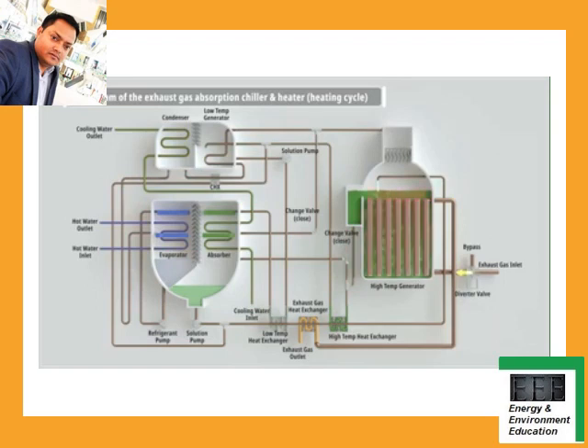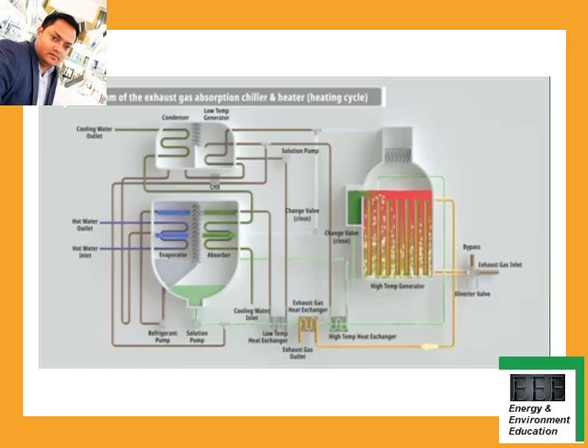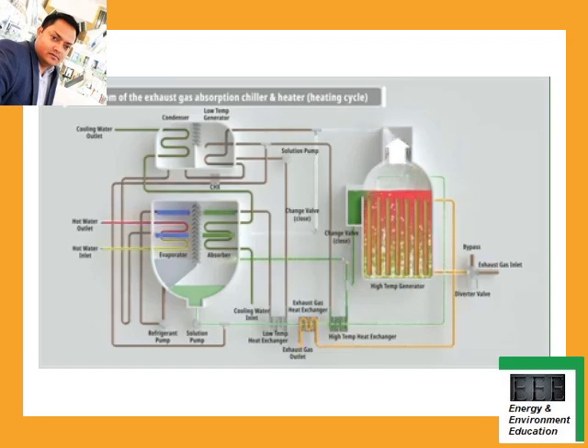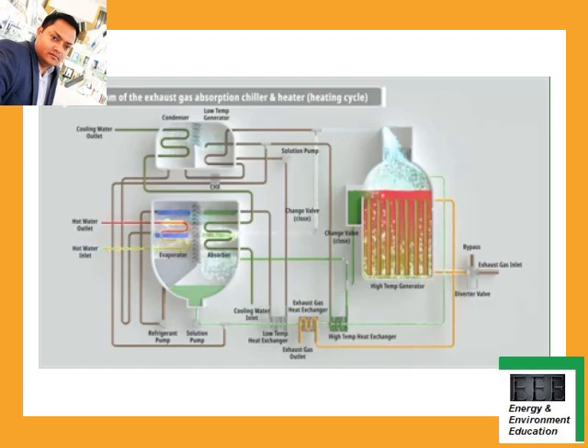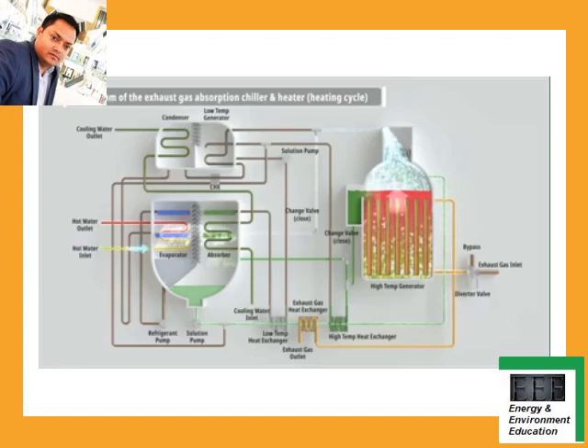The CHP system's heating works in simpler logistics. Heated by incoming exhaust gas in the high-temperature generator, the solution releases refrigerant into vapor, becoming concentrated solution, which flows to the absorber. High-temperature vapor flows to the evaporator, heating up incoming hot water. The vapor, condensed to liquid by releasing heat, is then mixed into the solution in the absorber and flows to the high-temperature generator, repeating the cycle.